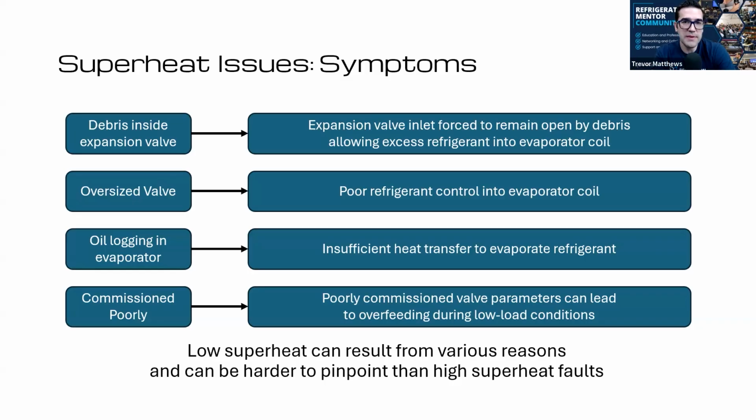They've worked on HFC units before, but they didn't have so much the controller and the superheat, being able to see it as much. And now I'm teaching them how to get into the trend graphs. One of my favorite ones is opening percentage of the valve. You go to the trend graph and they'll bring it up and I'll say, okay, let's go back 3 months or 4 months and let's look at the trend graph of that valve opening and what the superheat was.